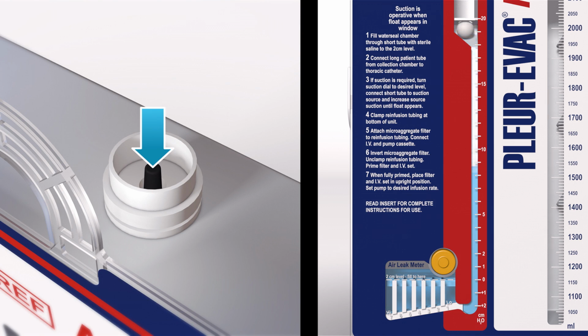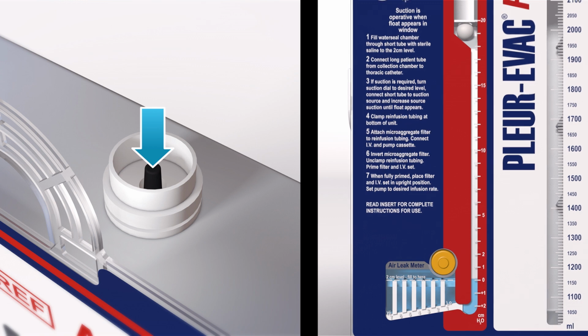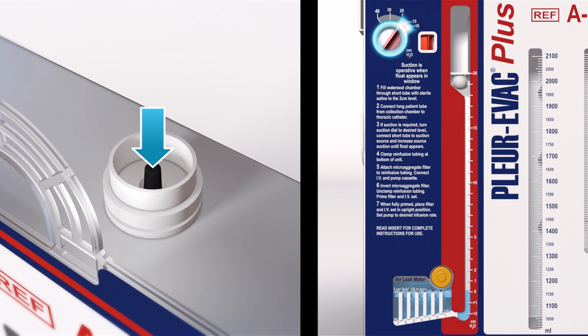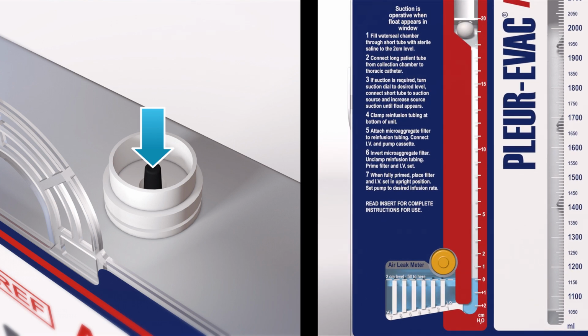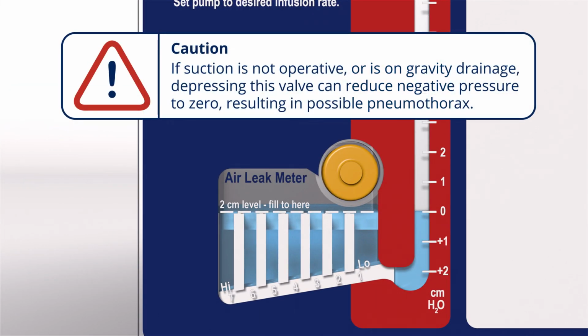Observe the water level in the water seal chamber drop until it reaches the desired level, being sure not to let it drop below 0. By depressing the valve, filtered air enters the unit. Now the patient negativity is at the new lower level as set on the suction control dial. The high negativity relief valve can be used anytime to manually vent excess negativity. Note that if suction is not operative or the patient is on gravity drainage, depressing this valve can reduce negative pressure to 0 or atmosphere, with a resulting possibility of a pneumothorax.